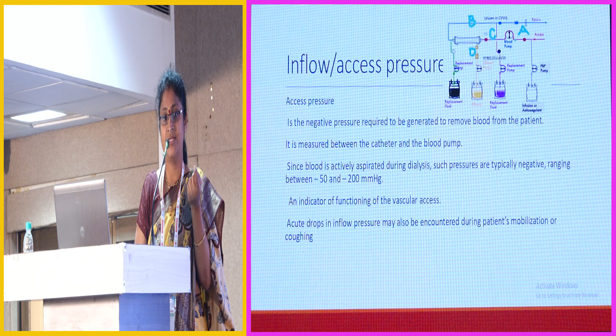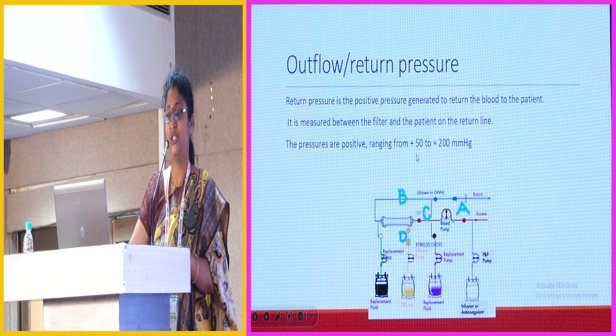The next is the outflow pressure, which is the last one. This is the return pressure. It is the positive pressure generated to return the blood to the patient, and usually it is between plus 50 to plus 200. And the filter pressure is between the blood pump and the filter. So this diagram C represents the filter pressure. It is the highest pressure point because we are pushing the blood through the circuit. We want the highest diffusion, the highest convection. So it indicates the functional state of the hemofilter and hollow fiber membrane.